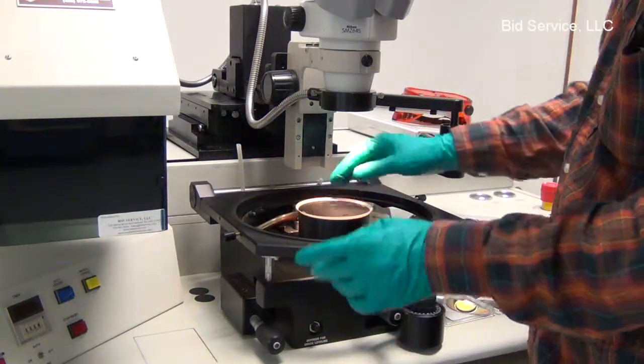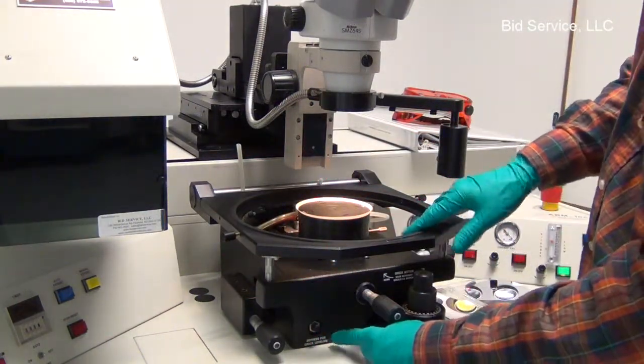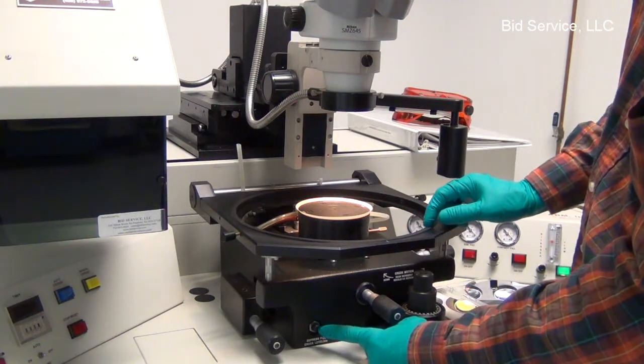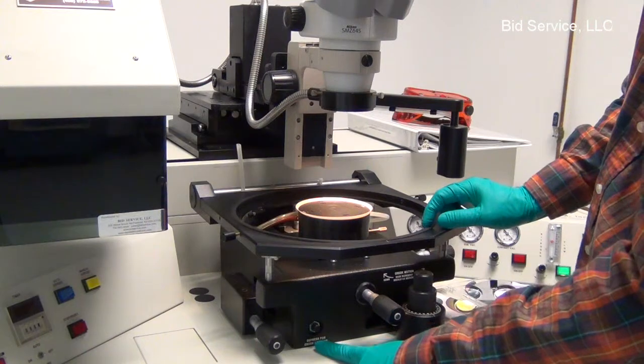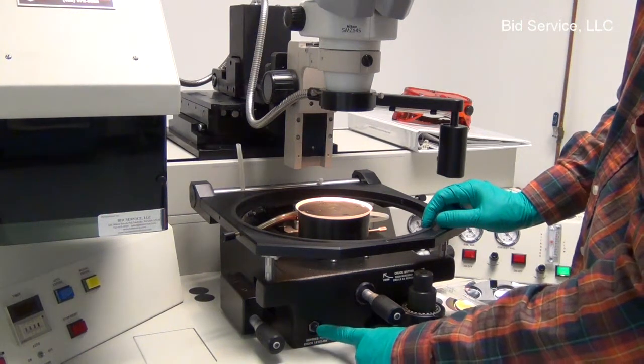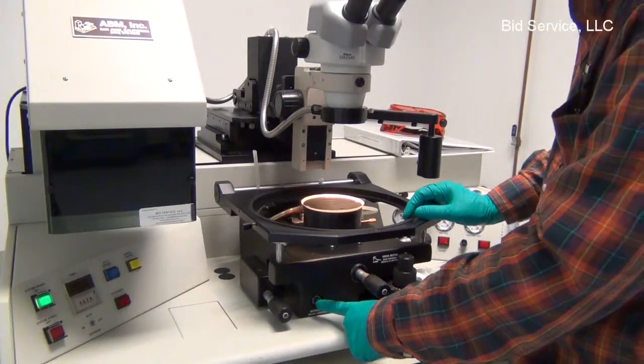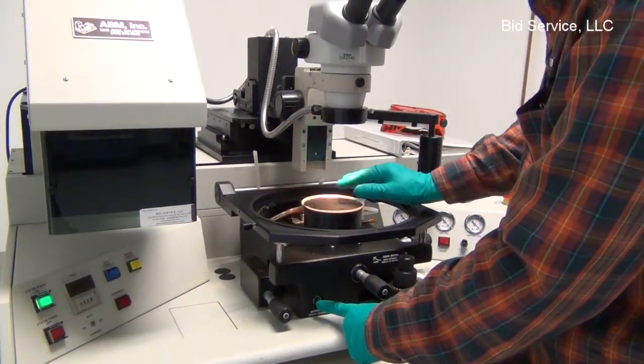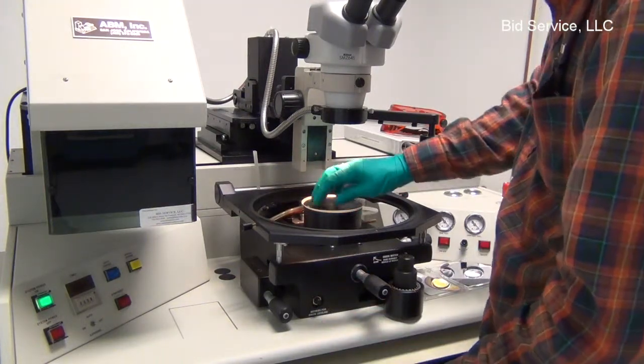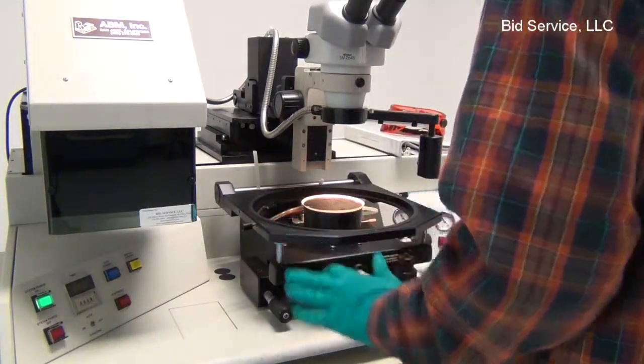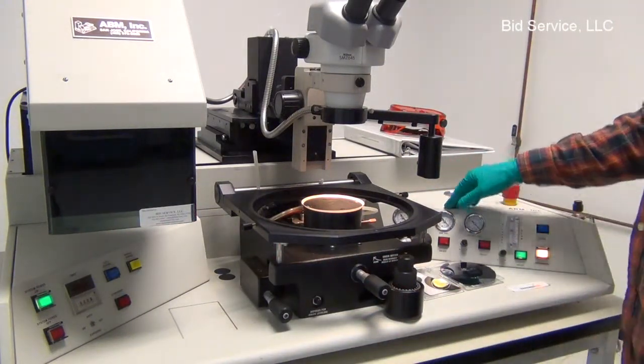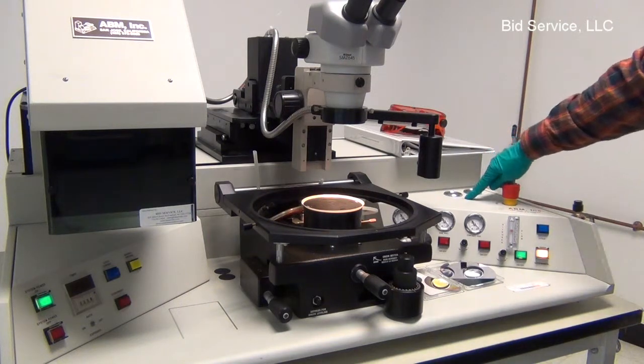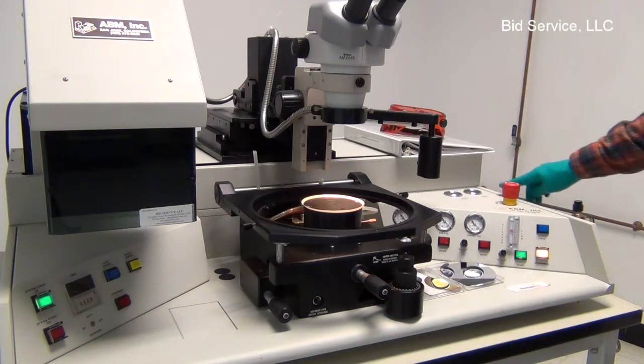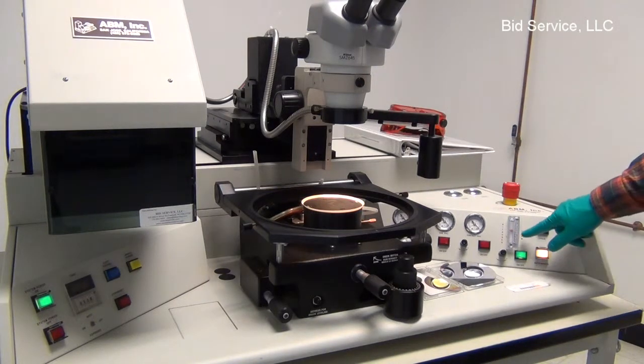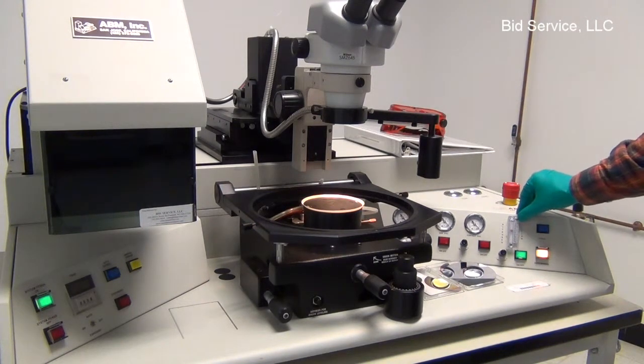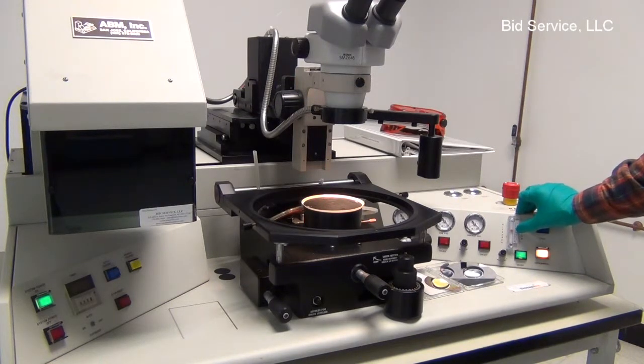to be used when leveling the chuck parallel to the mask, and while leveling, the chuck leveling button in the front is to be depressed, so that when we press it, the chuck becomes free, and once you release it, it is locked in that position on the vacuum condition. The unit requires about 25 inches of vacuum. We have a gauge for system vacuum and system pressure about 50 psi, and also nitrogen about 10 to 15 psi.